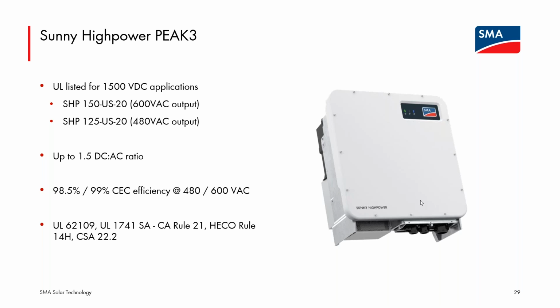So there most definitely will need to be a combiner box used with these inverters. There's not a combiner box included, but it is a single tracking channel inverter. And again, we're aiming for less flexibility on design as a trade-off for exceedingly high efficiency. So very, very high. Again, these are weighted efficiency, not peak efficiency numbers for the 2 power classes. So very enthusiastically adopted inverter for projects up to, I think, our current plant size limit for the PEAK3, or the highest capacity one that has been installed with the PEAK3, is 70 megawatts. And I think in early 2022, we're going to go past a 100 megawatt plant site with the PEAK3 inverter. So it has been rather enthusiastically adopted to very large megawatt sizes.